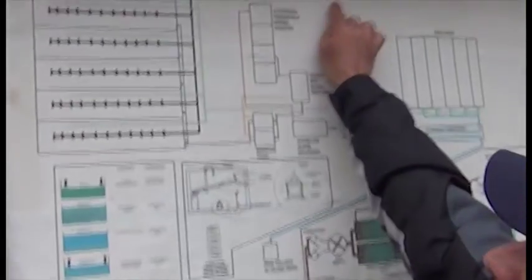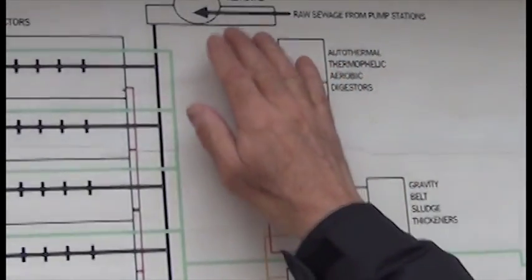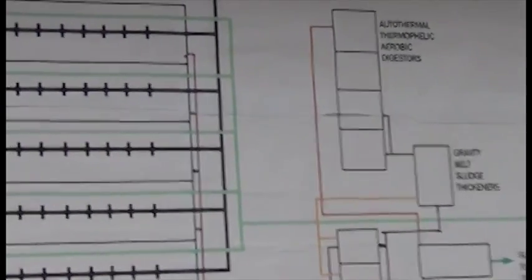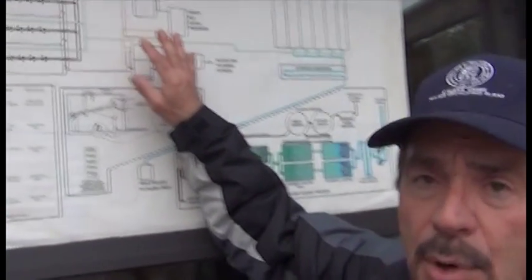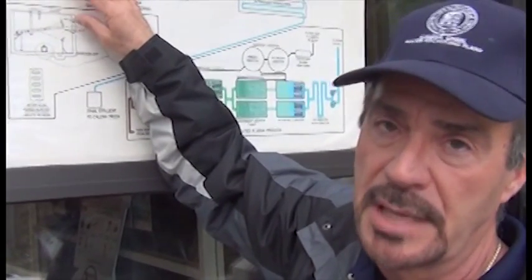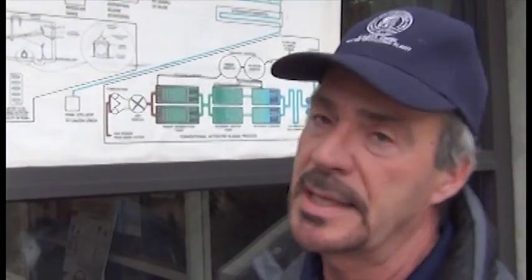The flow diagram goes this way. Water comes in from pump stations throughout the city and is pumped here. It goes through grit removal first. Grit removal is where we remove the inorganic material — things like rocks, sand, and gravel. This stuff can't be eaten or burned and has no value, so we remove it because it can only damage equipment down the line. When we remove it, it comes off with some organic material, so we wash the grit to get rid of that. Then the grit falls into a hopper and is taken to Ox Mountain landfill for disposal.